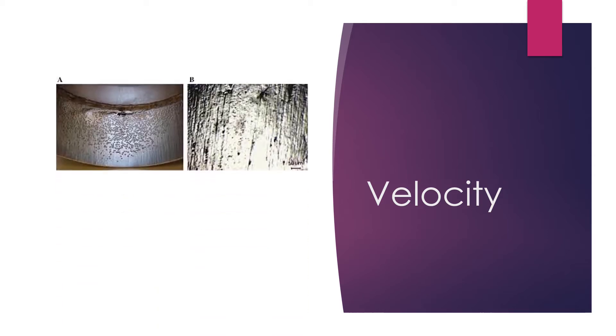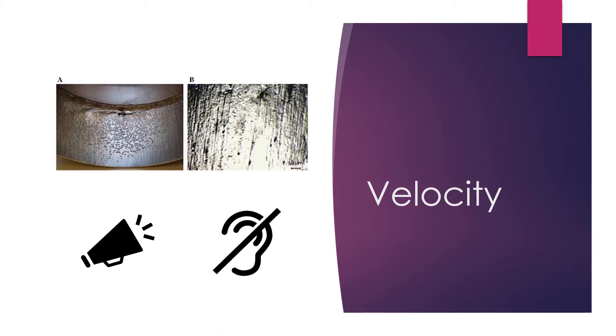High velocities can cause line erosion. Even sometimes, liquid high velocities can be a cause of corrosion in the pipe. High gas velocities can cause high noise — this noise can be too high to the point that it can affect the human ear if it is continuous. For gas or a two-phase line, maximum allowable velocity depends on fluid density, which means momentum, or in other words, the rho v squared value.